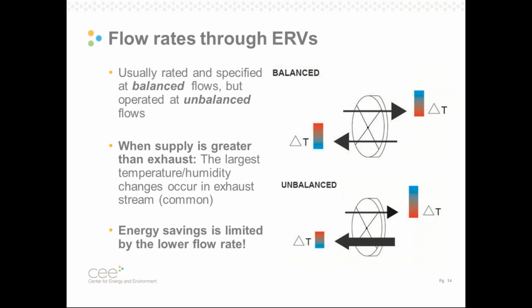In practice, though, what we find is usually supply is greater than exhaust. Not all the exhaust air comes back to the ERV. Say we have 1,000 CFM of supply, we only have 900 CFM of exhaust. In this case, we'll actually see a bigger change of temperature or enthalpy in the smaller flow stream, so in the exhaust stream, and a smaller change in the supply stream, and this is sort of common. But the really important takeaway here is the energy savings are ultimately going to be limited by the lower flow rate. If we have 900 CFM coming back instead of 1,000 CFM, we're going to reduce our net energy savings by about 10%.